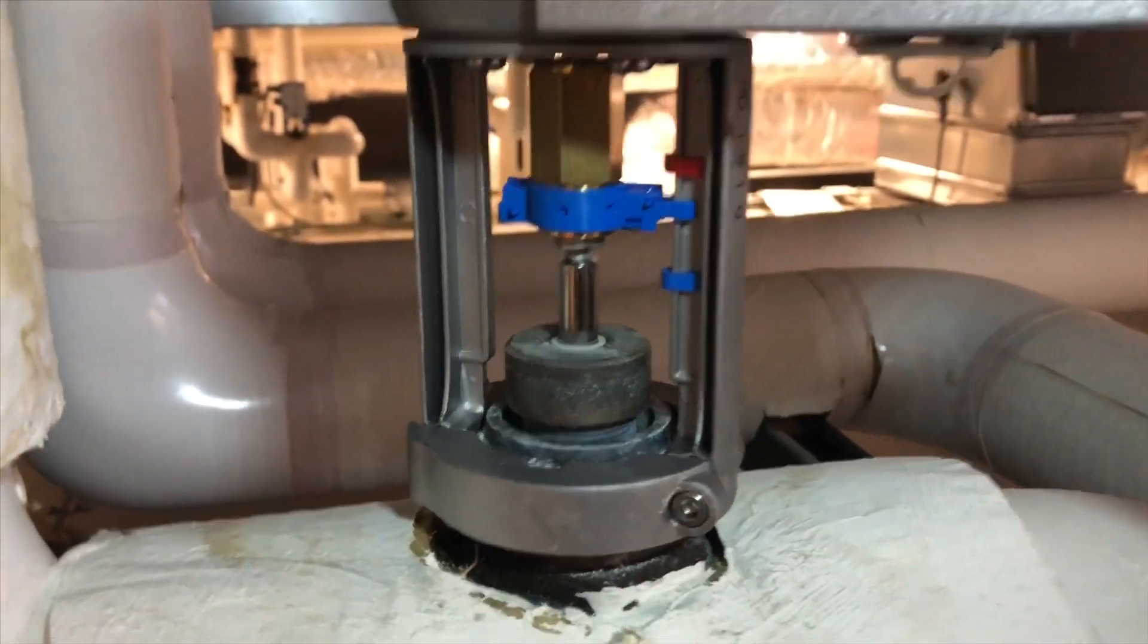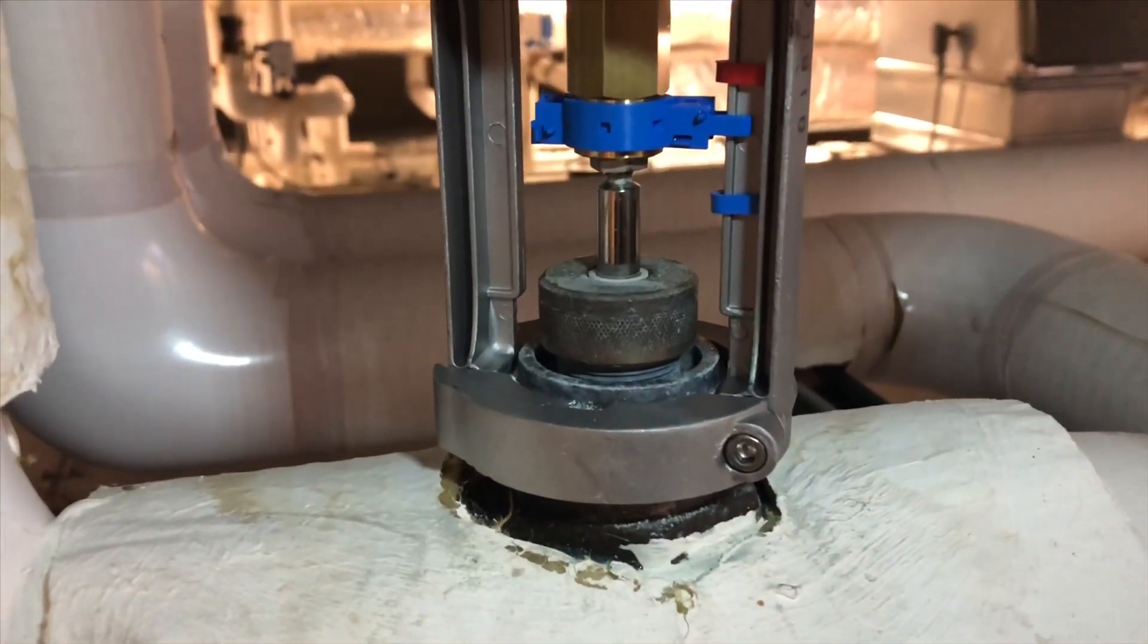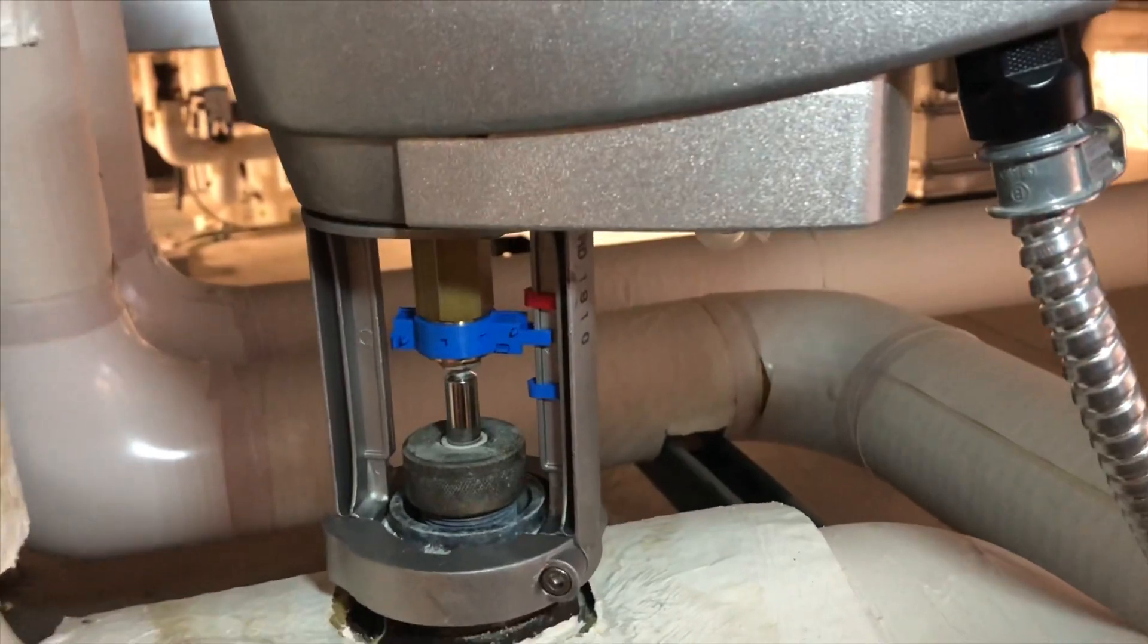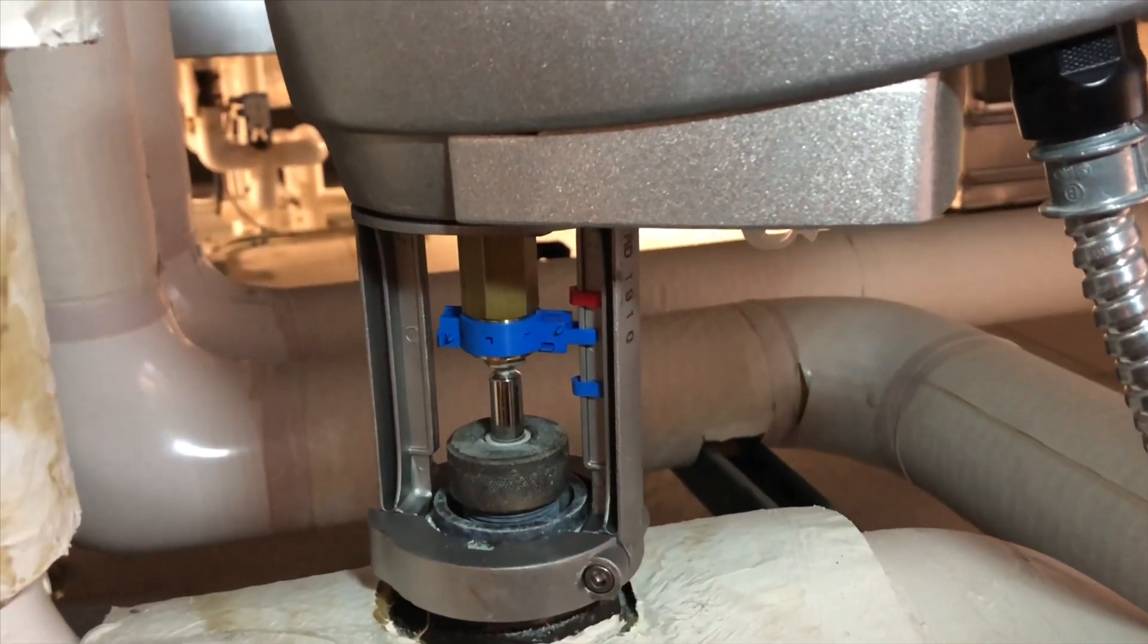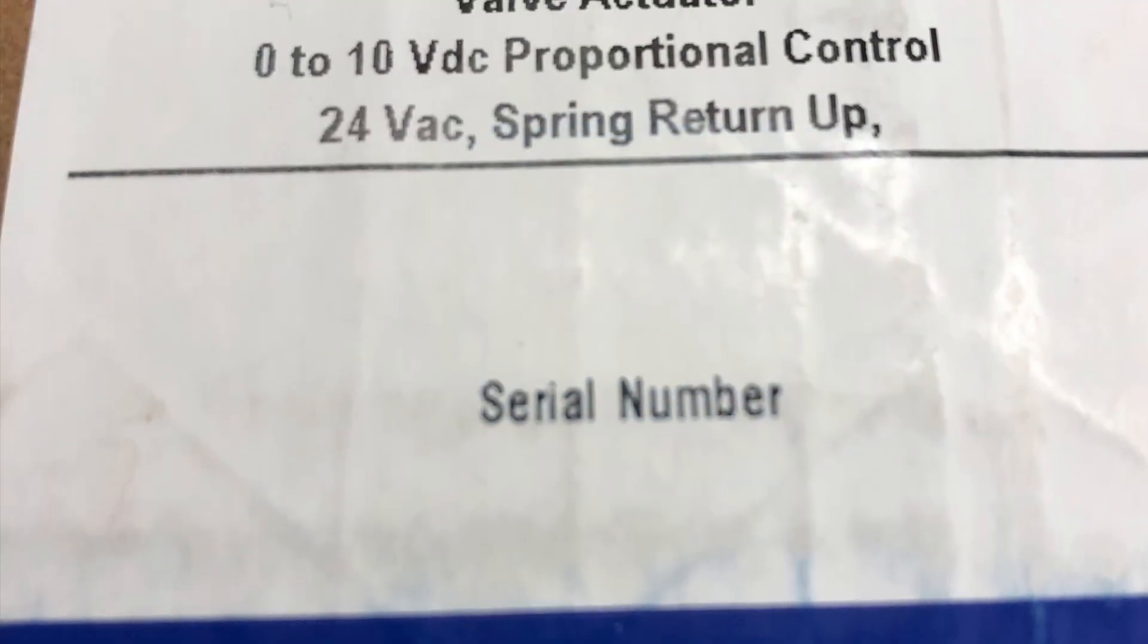Now that we've reversed, our cooling valve is now going to the open position, which is down. Which is proper function for this application. Now we're going to put our cover back on and tighten the screws back up.